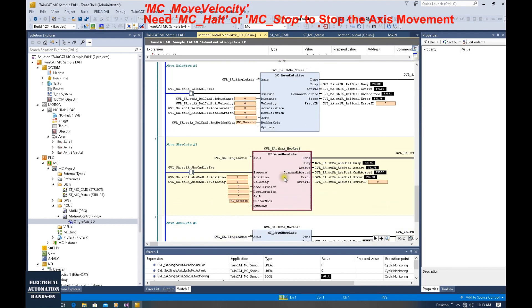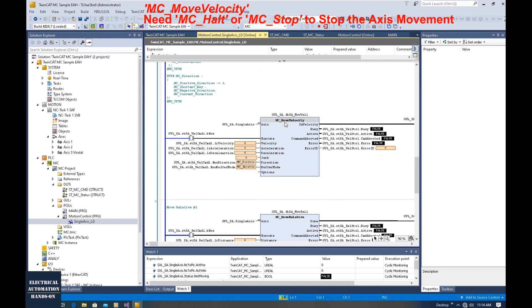For move relative and move absolute motion control, they don't have this problem. For move relative, it runs the distance you specify, and once it achieves that distance, the movement will stop. The same thing for move absolute — once it reaches the target position, the axis will stop itself. However, for move velocity, this is speed control. Once we fire this axis, the axis will keep moving and cannot stop by this command, so we have to involve MC Stop or MC Halt.